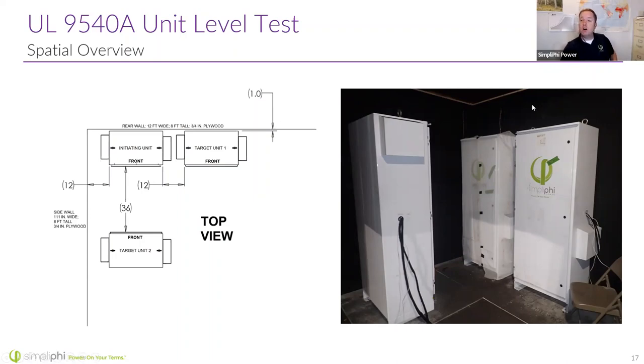If you notice, we chose plywood as our walls - imagine this is your garage. We chose an 8-foot ceiling rather than a 12-foot ceiling, and smaller spatial distances - 12 inches between a wall, 12 inches between units, mainly for the rain hoods, and 3 feet between units for working clearances. We wanted to pack these battery cabinets into the tightest space possible so that you, the installer, out at somebody's garage or utility room or battery room, can fit these into a small space, since we've demonstrated they're safely able to live in these kind of tight spaces.